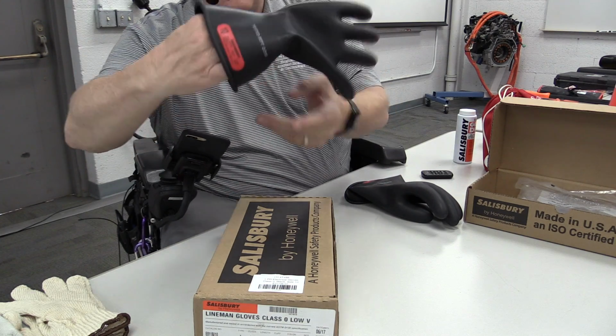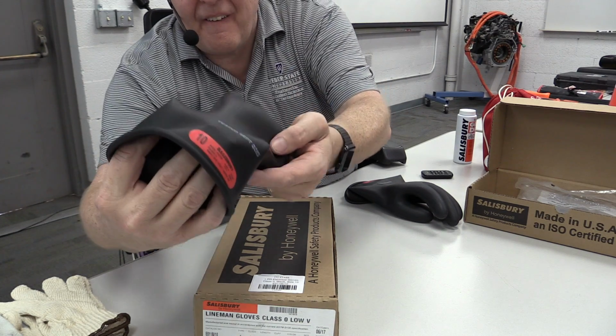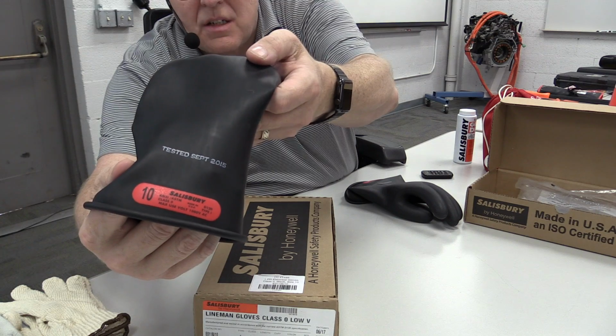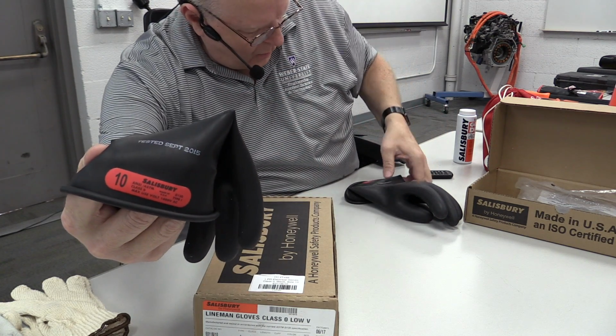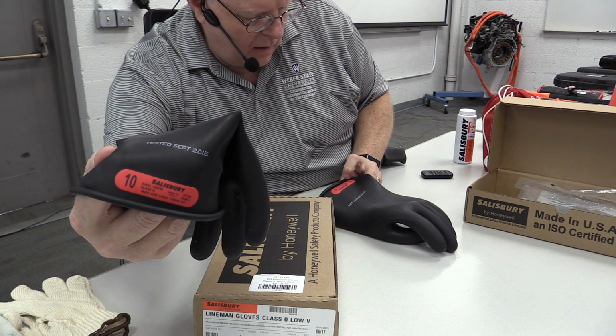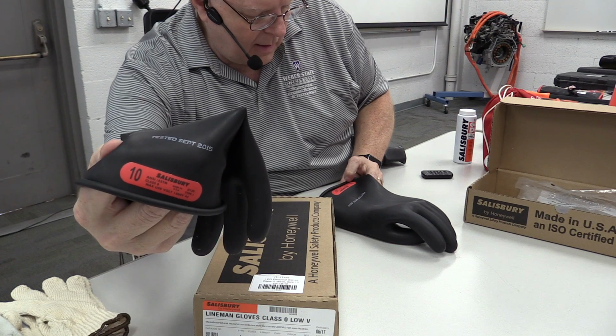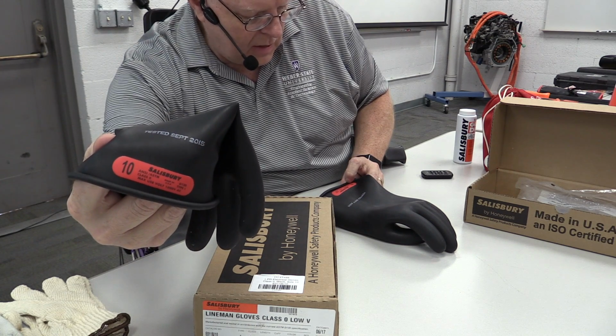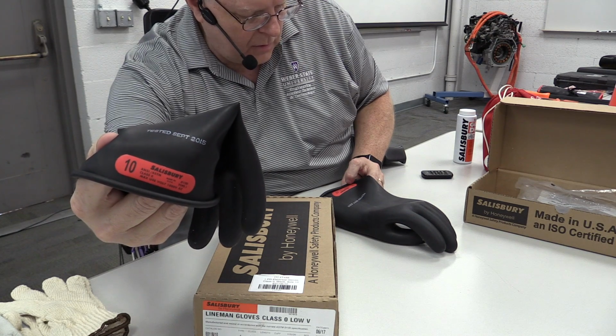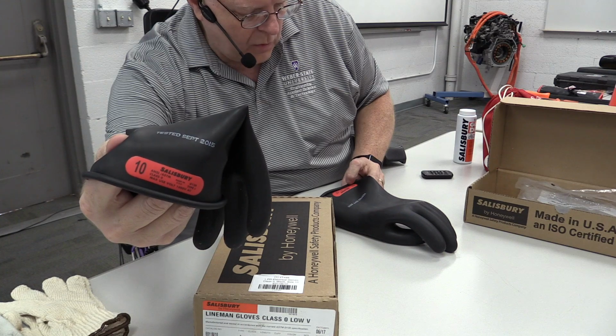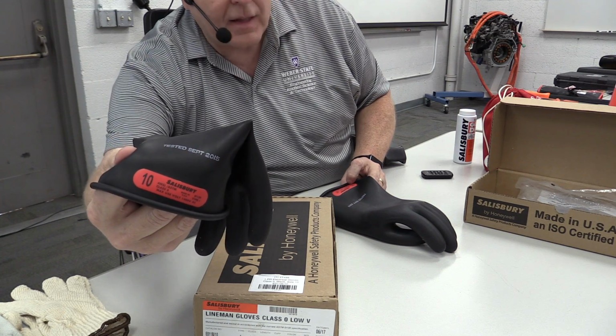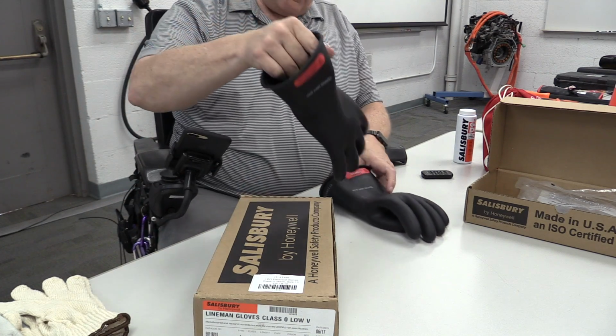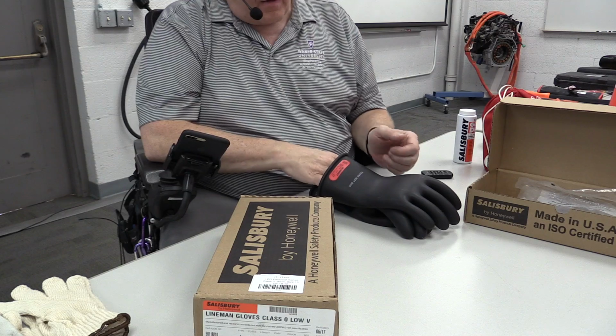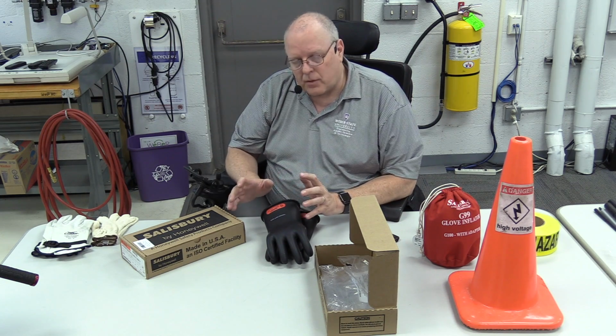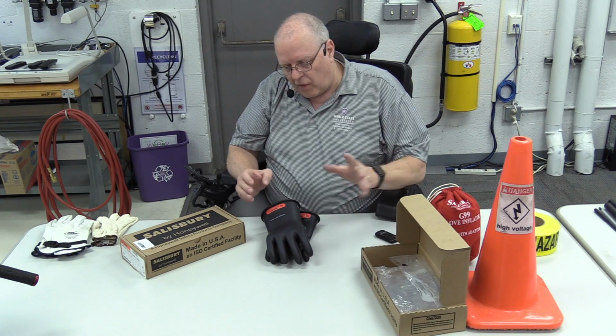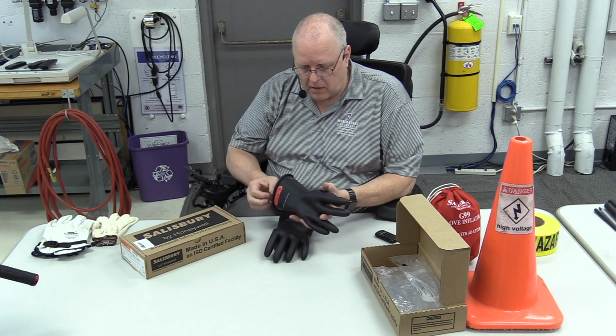It tells us right on the glove itself that it was tested September of 15, and the red tag tells us it's a size 10 glove. It has an ANSI and an ASTM standard, class 0 — there's also class 00 and other classes for different voltages. Maximum use voltage is 1,000 volts AC, which is considered low voltage in the electrical world, though voltages go much higher. For automotive, hybrid and electric vehicle use, the class 0, 1,000 volt glove is what you need.